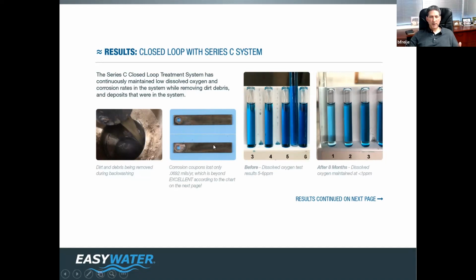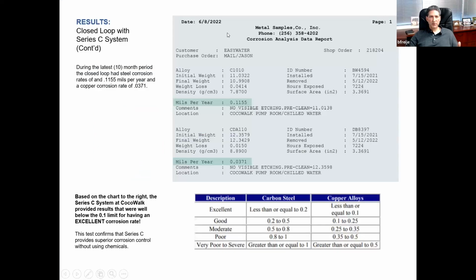Here's the latest coupons, corrosion coupons from the laboratory as of June of 22. What would your customers love to see as far as annual corrosion rate for carbon steel and copper? Well, for carbon steel, what's excellent but rarely achieved, 0.2 mils per year or less. We're about half of that, 0.1155. How about copper? Your customers would love to see 0.1 mils per year or less. We're about a third of that.